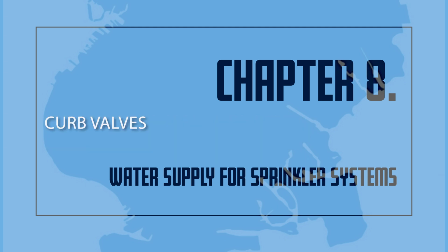Curb valves. Gate valves of the non-indicating type are provided in water distribution systems. Gate valves allow the sprinkler system to be shut off for repairs or maintenance. Such valves are normally a non-rising stem type. They are operated using a special key wrench. A valve box is located over the valve to keep dirt from the valve. The valve box also provides a convenient access point for the valve wrench to the valve nut. A complete record should be made for each valve in the system. This record should include the exact location, the date it was installed, the make, the direction of opening, number of turns to open, and any maintenance that was performed.